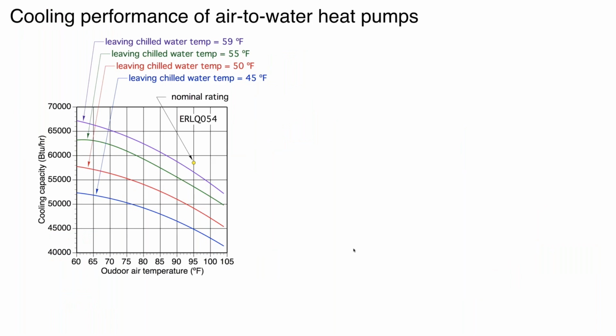Performance. And this is typical. This is a graph for a specific product, but what you'll find with heat pumps and cooling capacity is the warmer it is outside and the colder you're trying to provide this chilled water, the lower the cooling capacity is going to be. So we're looking at curves here that all dive down as it gets warmer outside. And then when we look at leaving chill water temperatures, 45 degrees, we would be on this curve.